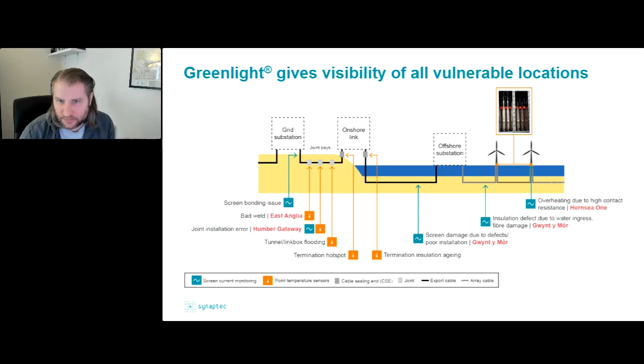Just to zoom in a little bit on what that looks like, it's important to note that DTS and DAS are often spec'd as the standard approach for monitoring cables at the moment. They do give you useful information about the cable integrity, but they tend not to give you any information about what's happening at the joints or terminations, because typically the fiber is routed around those locations. Whereas Synaptec's approach is to put the sensors at those weak points and see exactly what's going on. And we can place sensors as close as possible to these critical points.